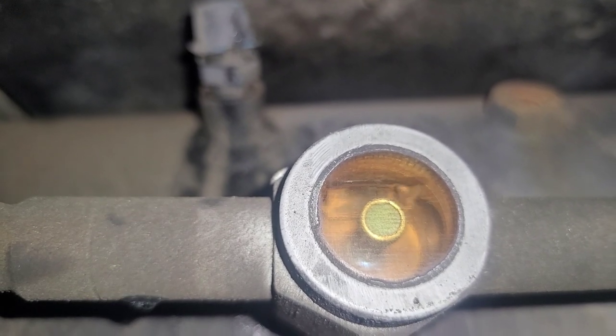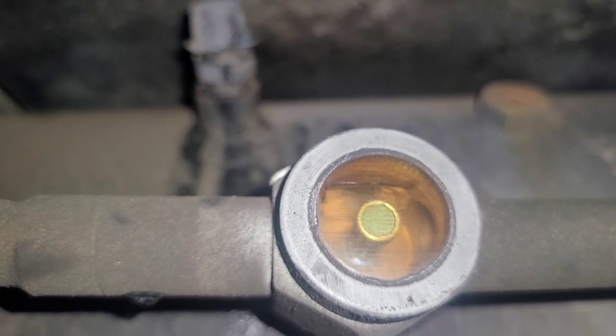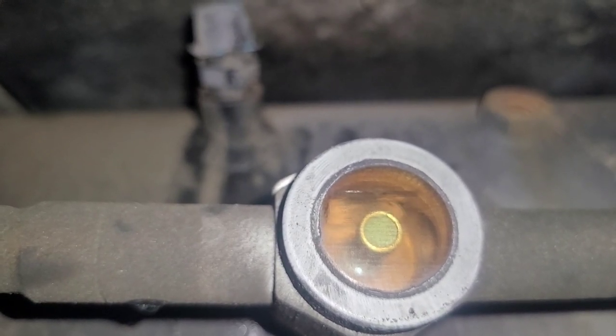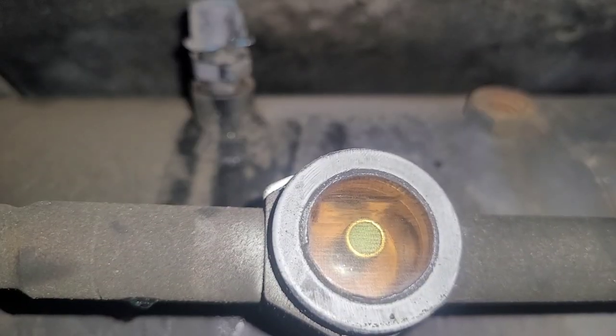Got my gauges hooked up to it, adding R-448 — it ended up taking a full jug. Had a leak on it, one that I couldn't just repair by tightening. Had to go get a new fitting in order to fix this. So I fixed it.